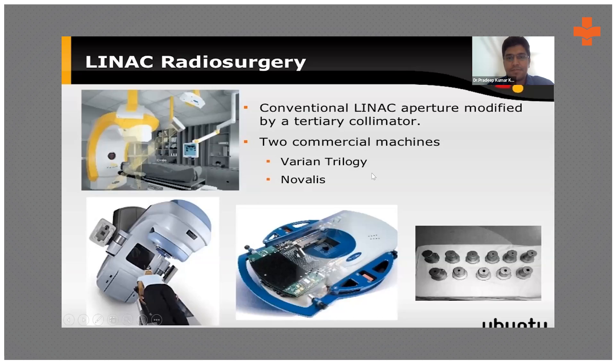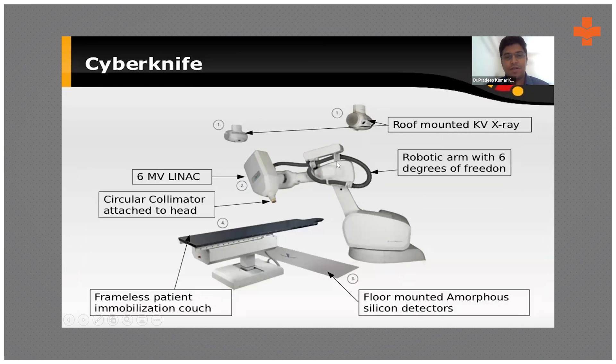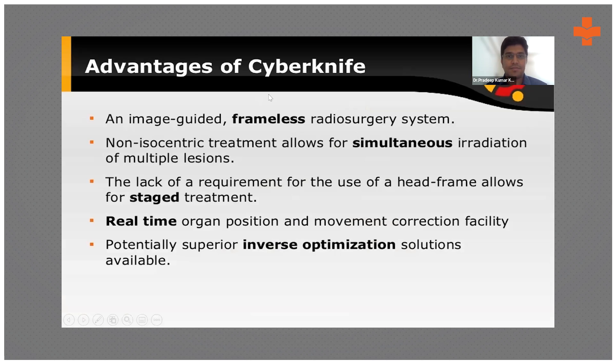This is the CyberKnife: a 6 MV linac mounted on a 6-degree-of-freedom robotic arm. It can move in any angle and can reach over a thousand nodes surrounding a particular treatment point, providing sub-millimeter accuracy and delivering high doses with very few side effects. Roof-mounted X-ray sources continuously generate imaging every 15 seconds to track the movement of the treatment area.